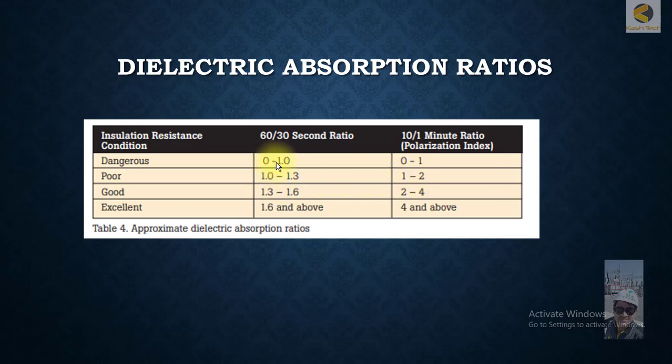If either ratio is between 0 and 1, whether for the second ratio or the polarization index, then the insulation condition is dangerous.